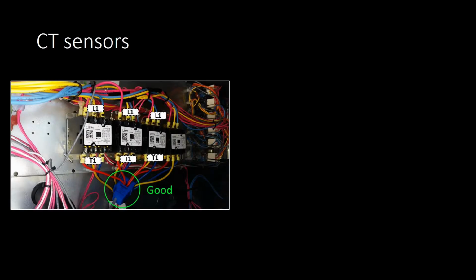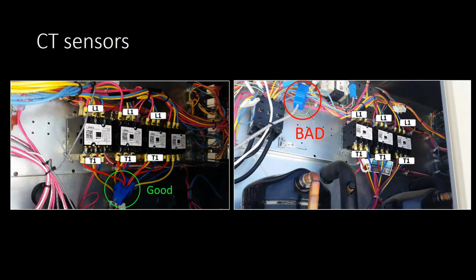CT sensors should always be installed on the load side of the contactors for compressors and fans. Find the wire labeled T1 and install the CT clamp around it. If there is more than one compressor, then install the CT clamp around the T1 wires of all compressors. If a motor is 3-phase, do not put the clamp around all 3 wires. For a 3-phase motor, just capture the T1 wire.